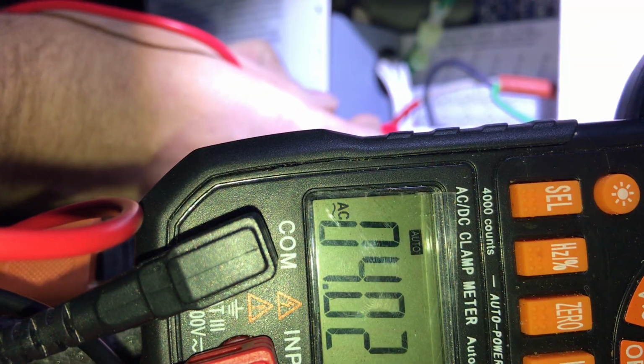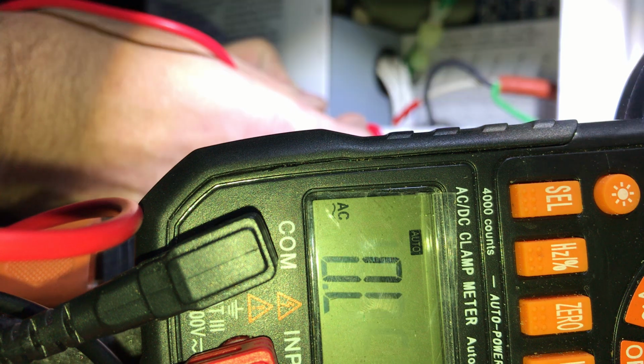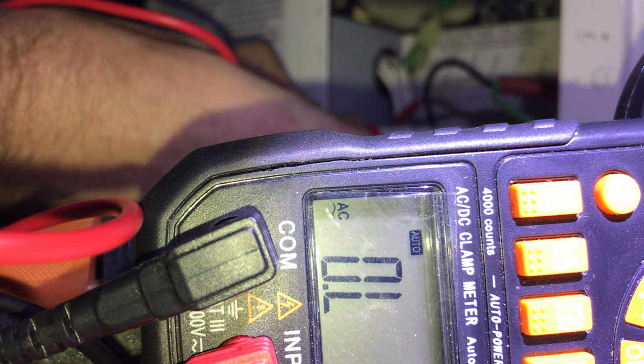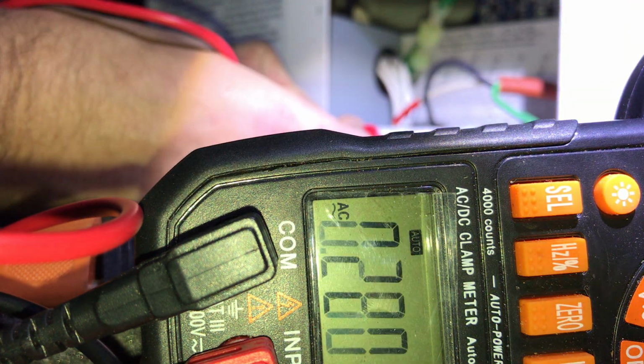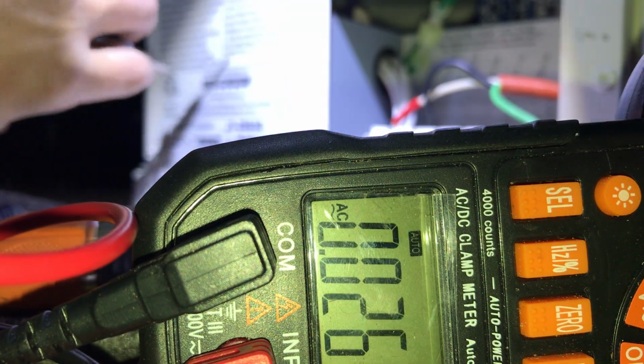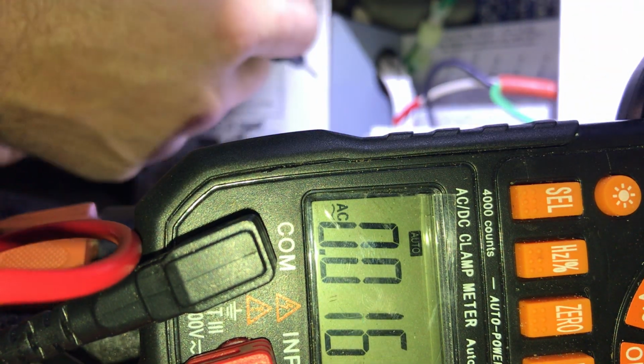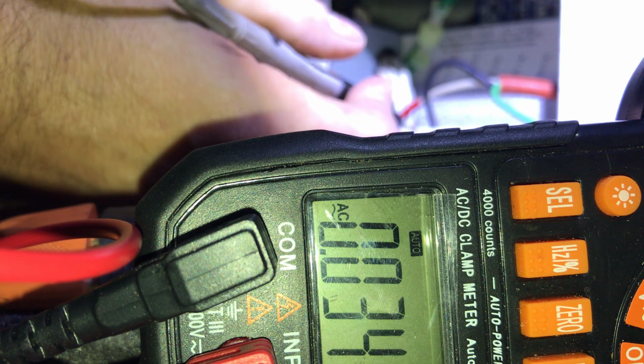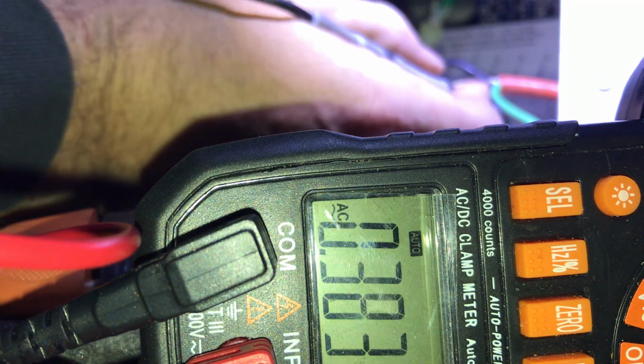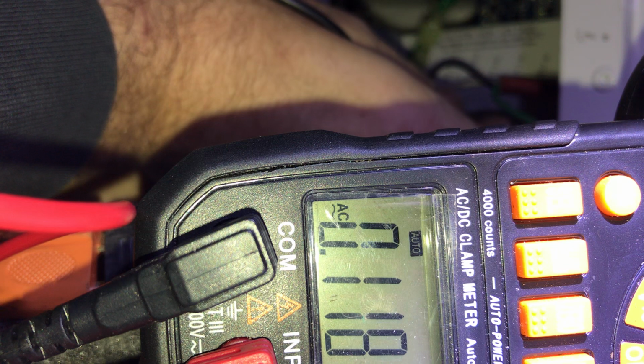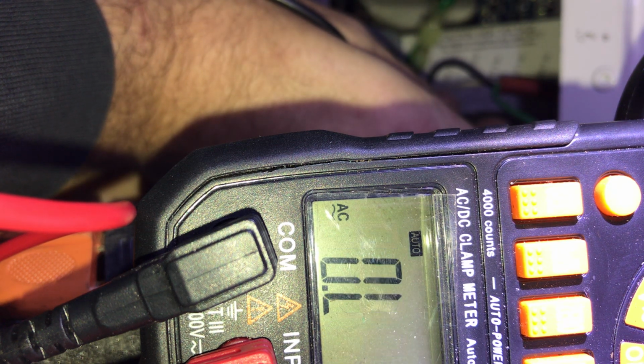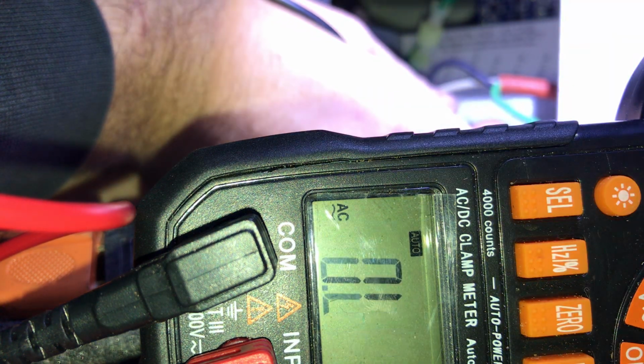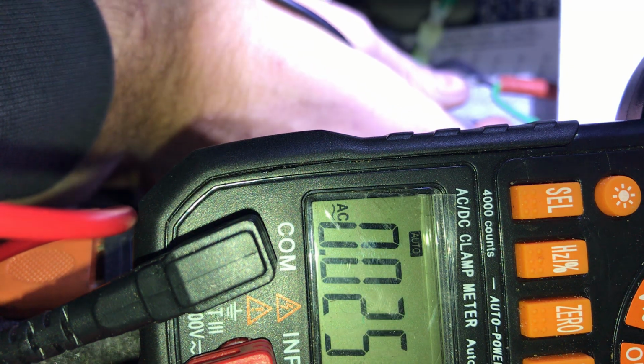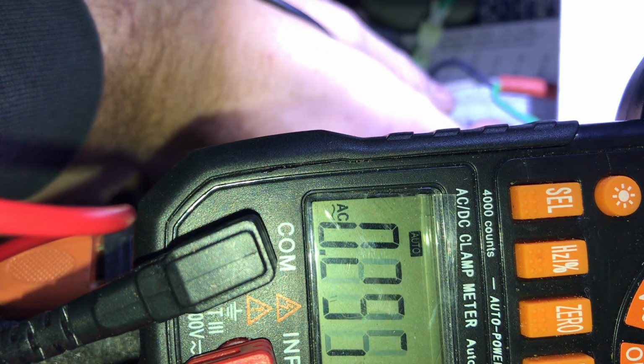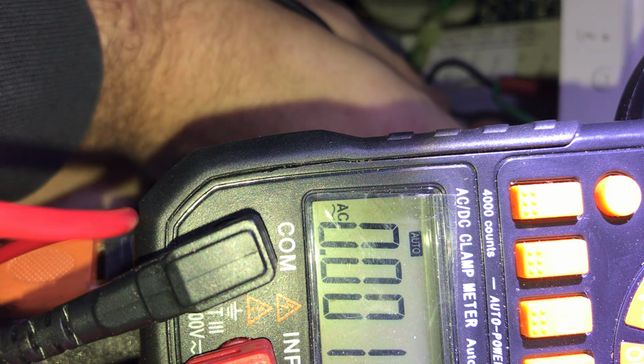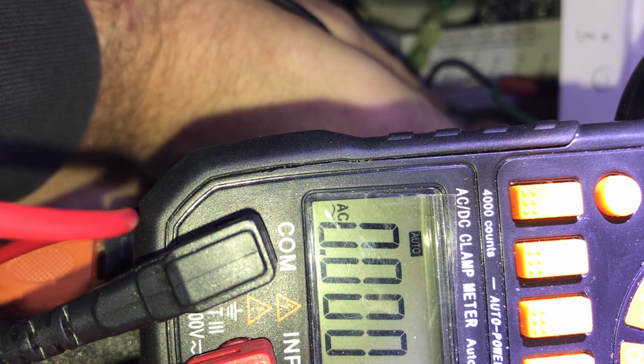I can also probe hot 2 out, which I'll do now. Same thing, it's bouncing around. And just for the hell of it, if I go hot 1 to ground instead of neutral, same thing, it's bouncing around. Now can I check the difference between ground and neutral out? Yeah, so ground and neutral out, 0 volts.